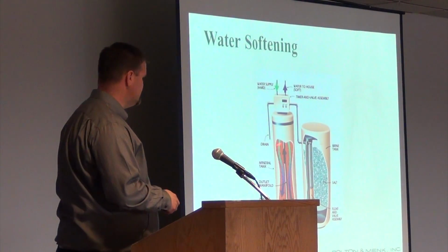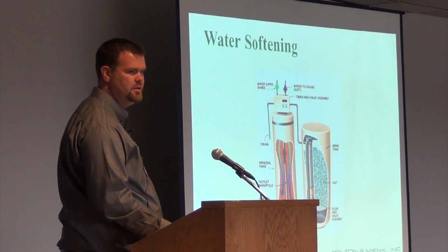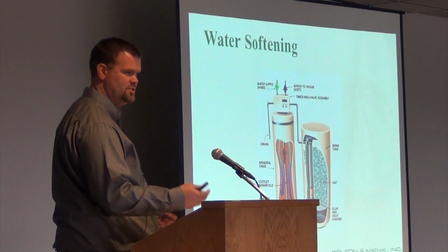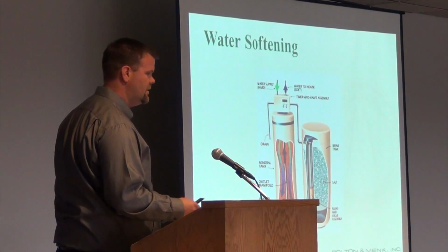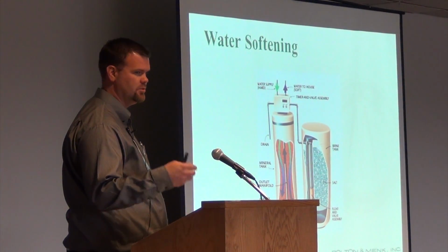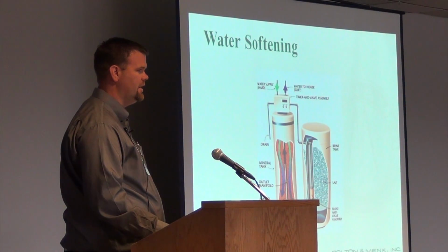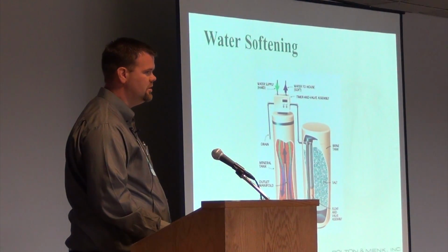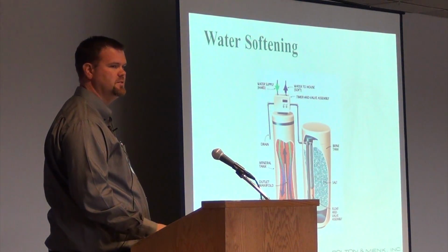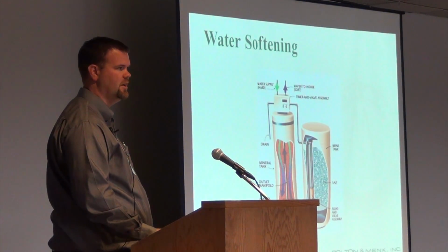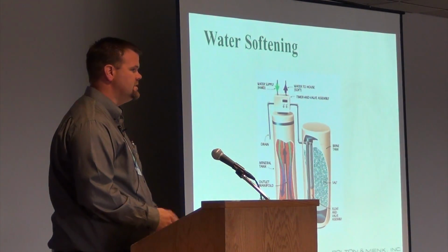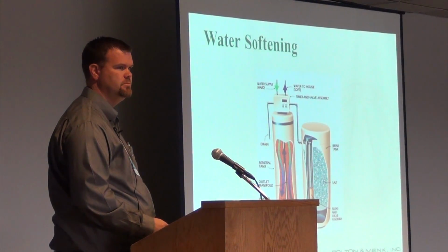Well, after time, the sites on these beads, their capacity to grab on to the hardness is no longer there, and so you have to regenerate again with this very high concentration of salt. That works great. It puts the sodium back on the beads for you, so it's ready to go. But every time you do that, the salt that you're using, I'm going to use sodium chloride, which is probably the most common, has got that chloride portion of it also, and that goes down the drain out to the treatment plants and contributes to the salty water discharge at wastewater plants. And so this is kind of the first example of how water treatment affects wastewater plants, the salty water discharge. This is a negative impact, and is one that is leading to the problem and can cause the problem in a lot of situations.